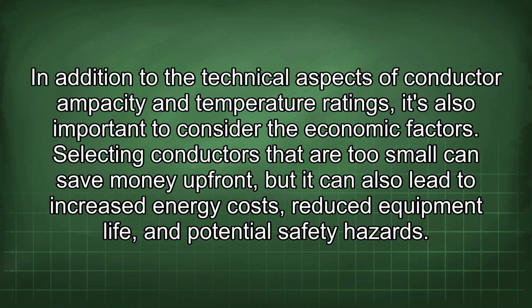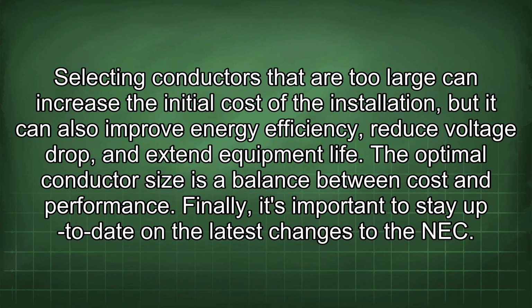In addition to the technical aspects of conductor ampacity and temperature ratings, it's also important to consider the economic factors. Selecting conductors that are too small can save money upfront, but it can also lead to increased energy costs, reduced equipment life, and potential safety hazards. Selecting conductors that are too large can increase the initial cost of the installation, but it can also improve energy efficiency, reduce voltage drop, and extend equipment life. The optimal conductor size is a balance between cost and performance.